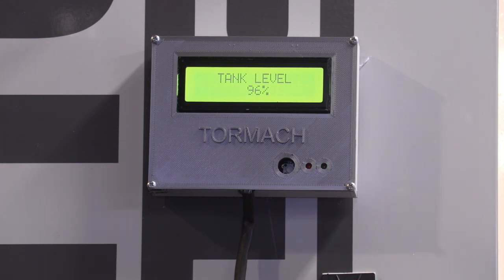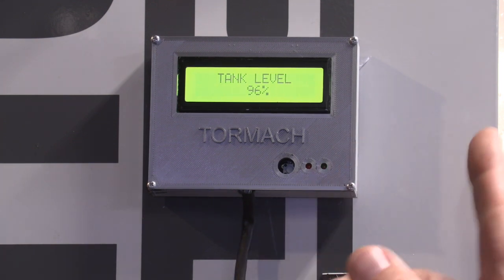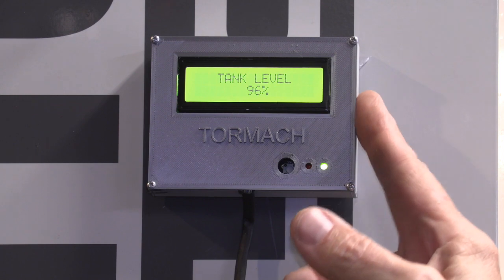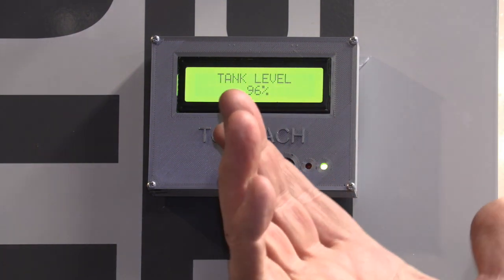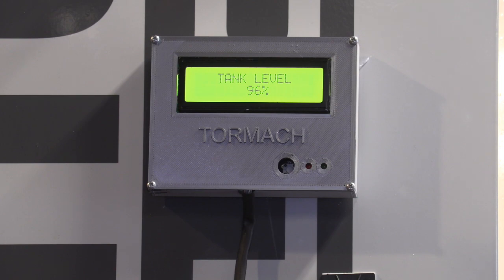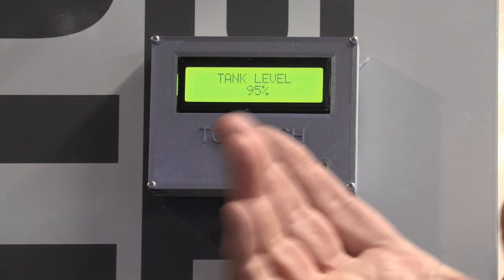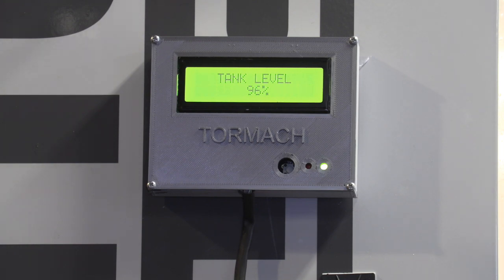This system is simple and straightforward, and it operates by having a float which is in the coolant tank, and the float moves the potentiometer as the float goes up and down with the level in the tank. The potentiometer sends a signal to a small microcontroller. The microcontroller formats that information and sends it up through this multi-conductor cable to this little plastic box with an LCD display inside, and it displays the current level in the tank. And I just filled this machine, so it's currently showing me that I've got 95% coolant level.